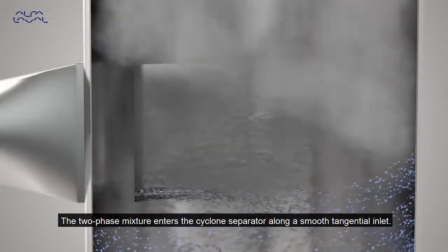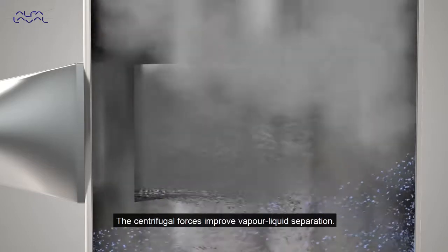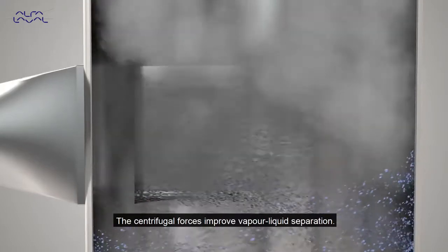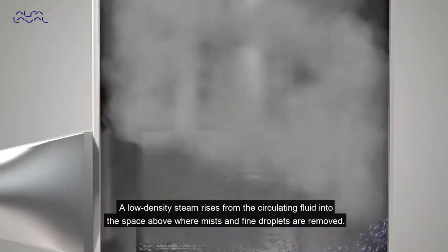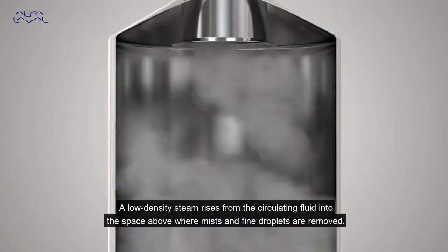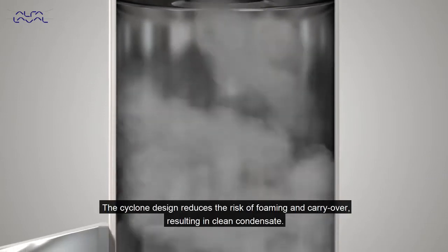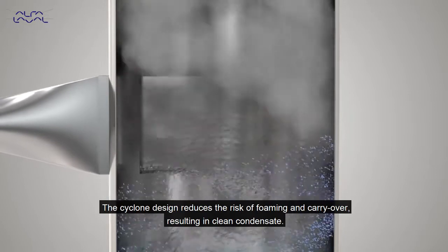The two-phase mixture enters the cyclone separator along a smooth tangential inlet. The centrifugal forces improve vapor-liquid separation. Low-density steam rises from the circulating fluid into the space above where mists and fine droplets are removed. The cyclone design reduces the risk of foaming and carryover, resulting in clean condensate.